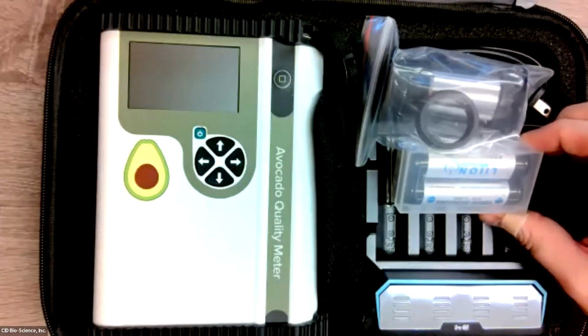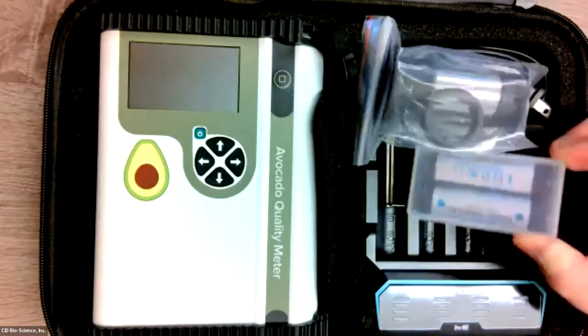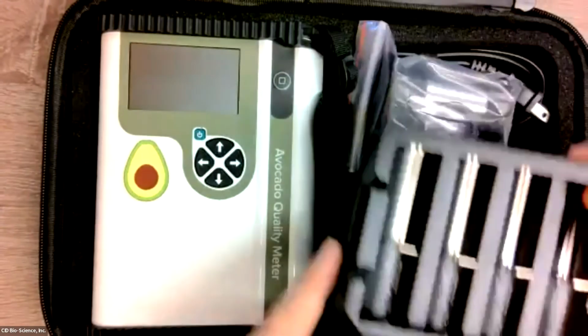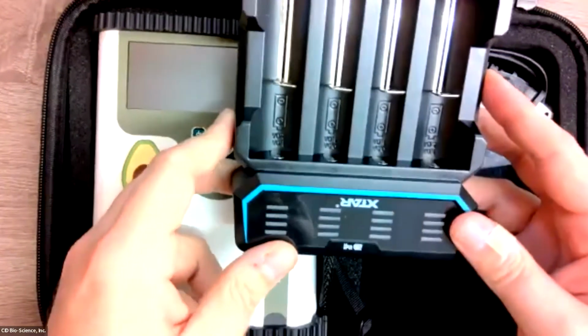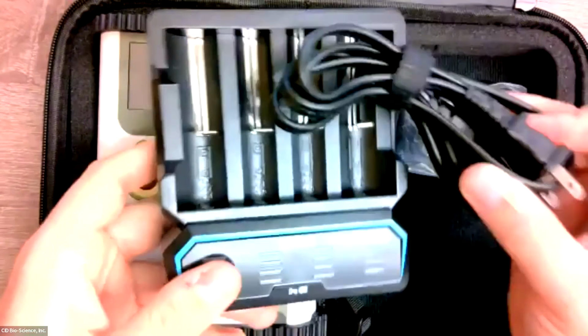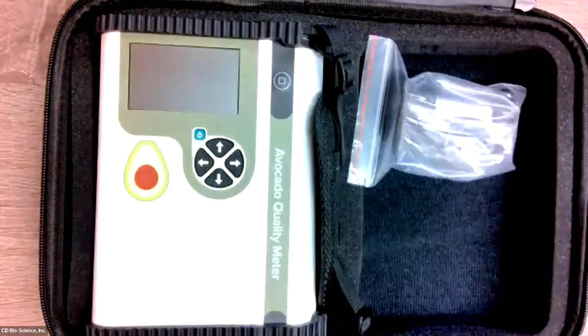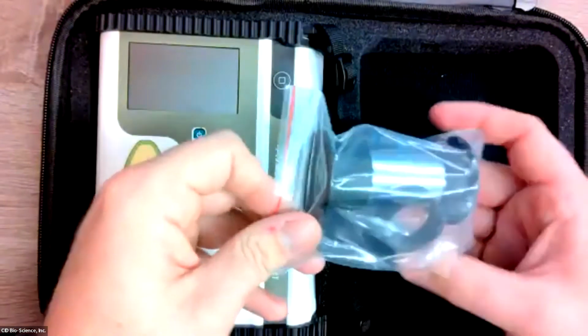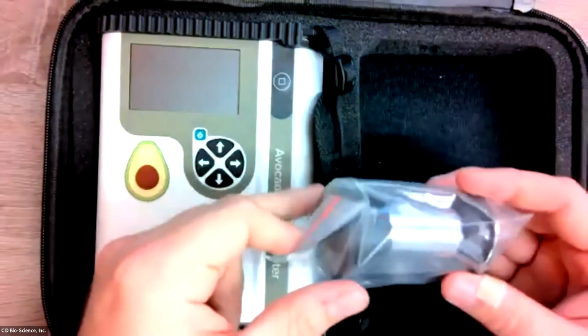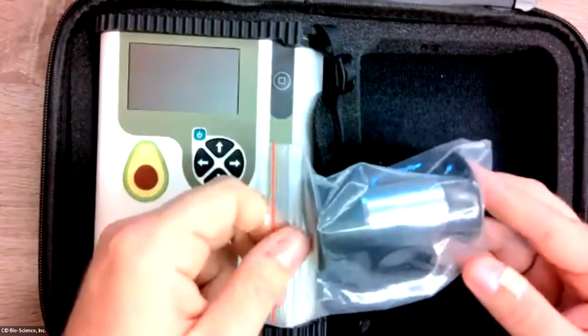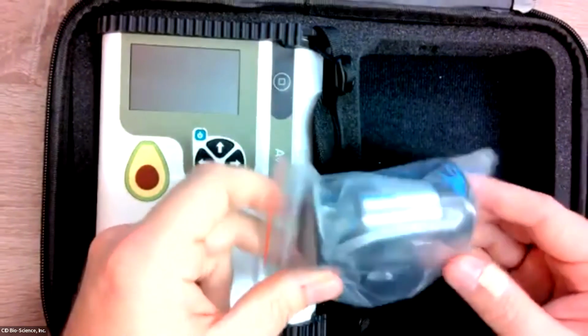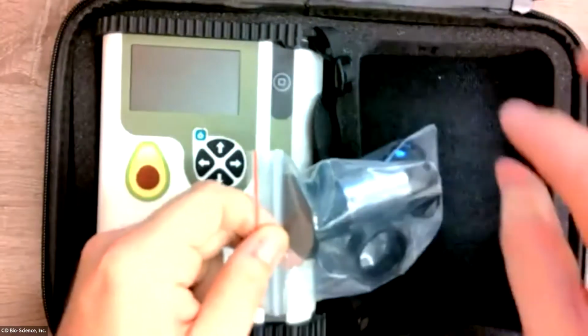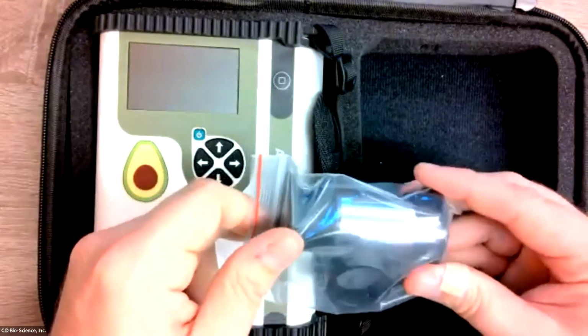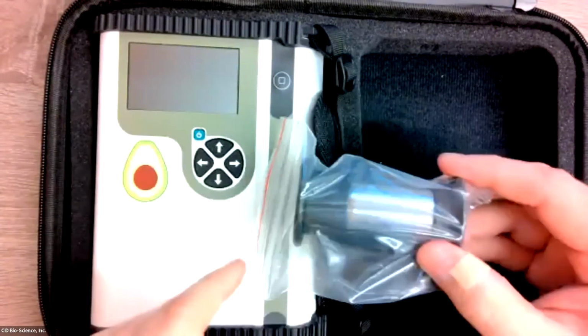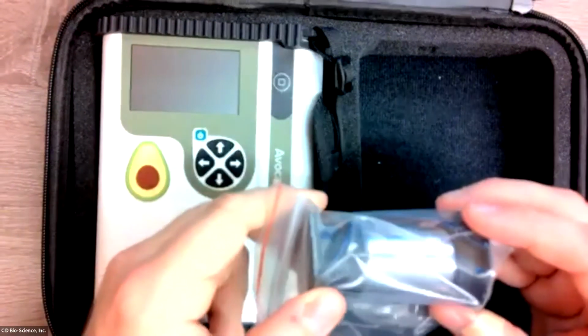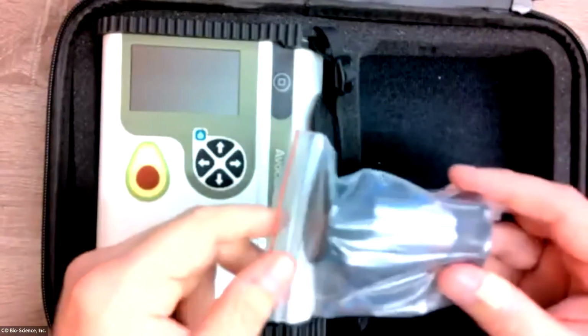So you'll have a spare set of rechargeable lithium-ion batteries. You'll have your actual battery charger. So this is where you can recharge your lithium-ion batteries, as well as the plug adapter to operate that battery recharger. This is a coring tool. So in the instance where you need to perform a calibration on your instrument, this is a tool that can be used to actually core out samples from an avocado to do destructive testing after you've scanned the avocado with the device. So this is a useful tool for your analytical lab testing if a calibration is necessary.